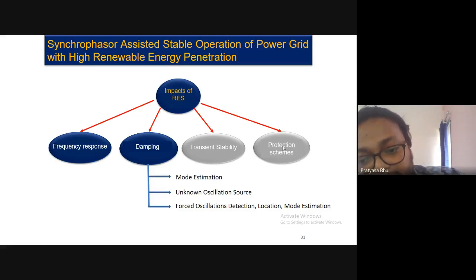Then you have forced oscillations. Forced oscillations are basically because of continuous oscillation inputs in the turbine controllers, in the stabilizer controllers, AVR controllers. There have been forced oscillation cases where there are some external inputs in the turbine controllers, and the system is continuously oscillating. Then it was tracked and found that one particular generator was causing those oscillations. So from measurements, how to identify the forced oscillations?